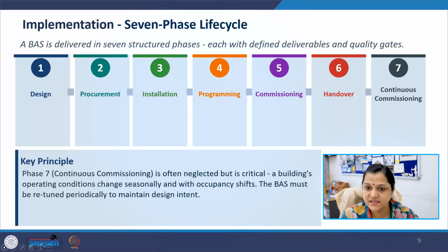So, a building automation system project follows a structured 7-phase life cycle. The phases are design, procurement, installation, programming, commissioning, handover, and continuous commissioning. Each phase has specific deliverables and quality checks. Many projects perform well during installation but fail during operation because the later phases are neglected. In particular, continuous commissioning is often ignored.